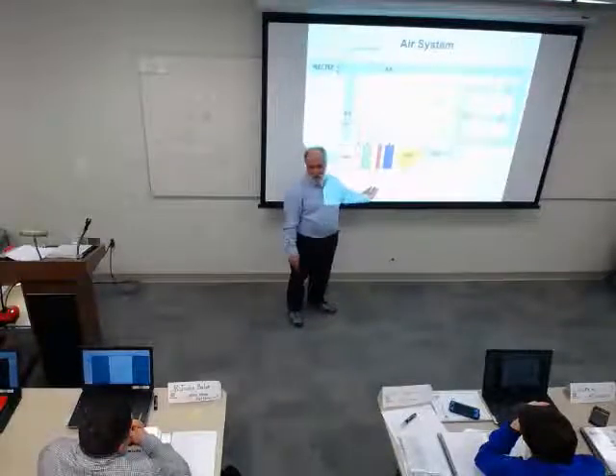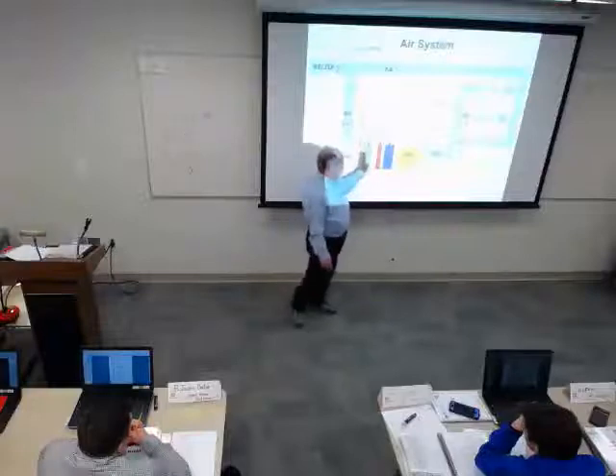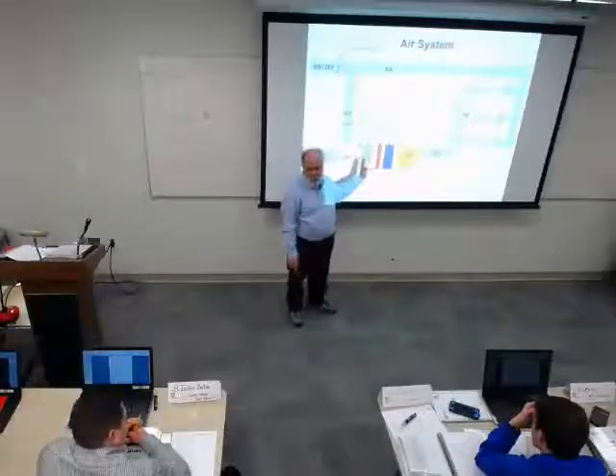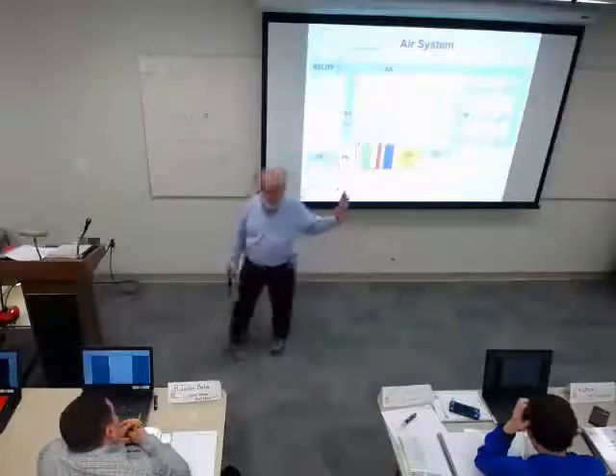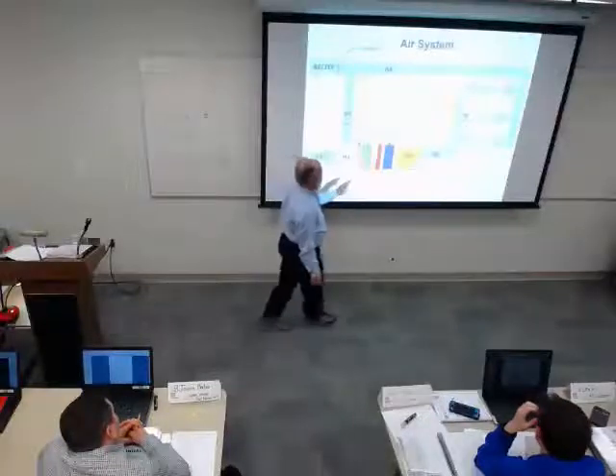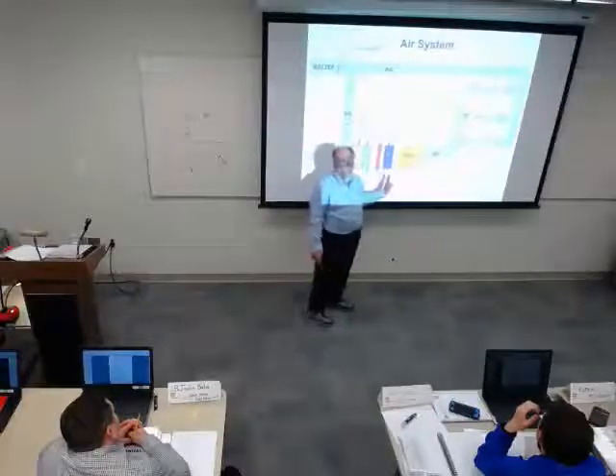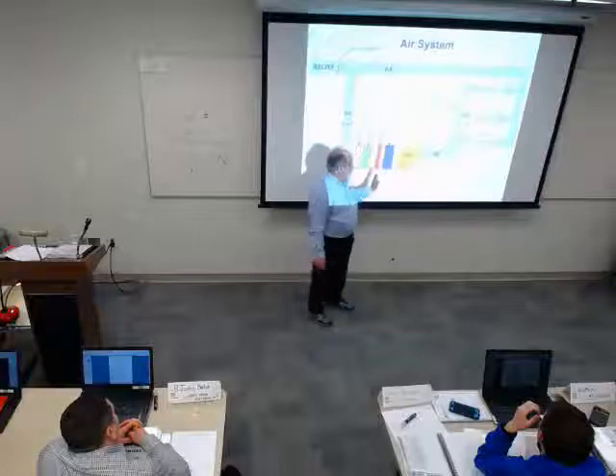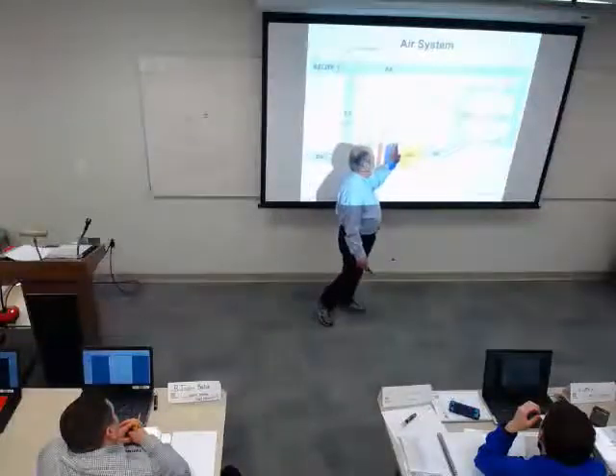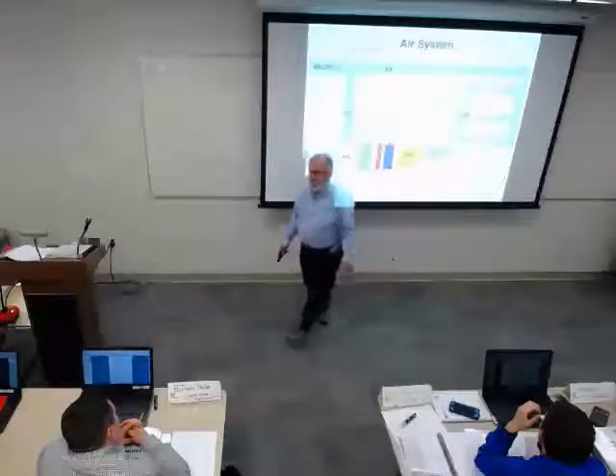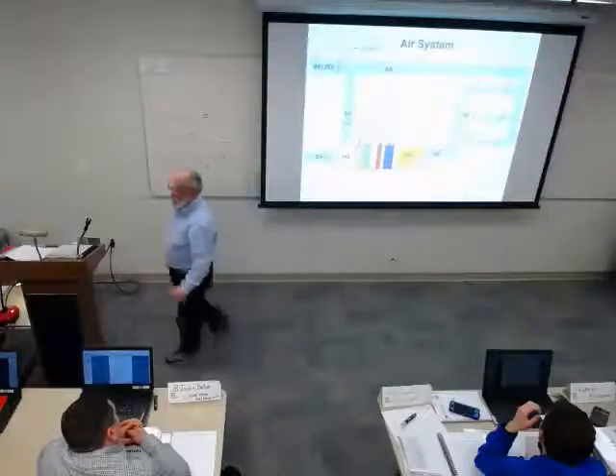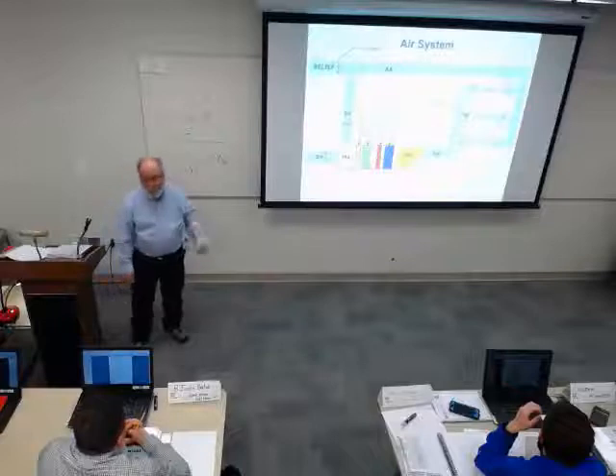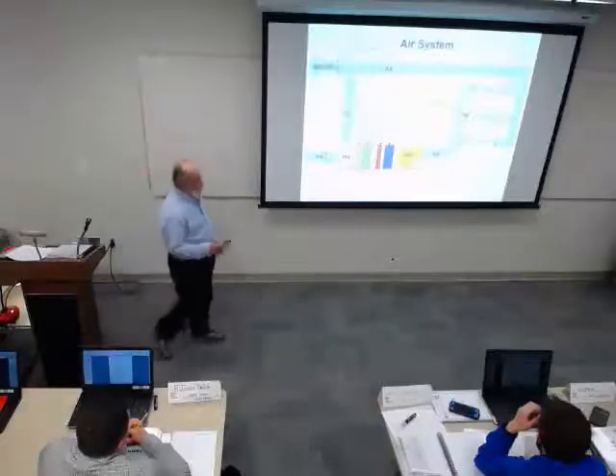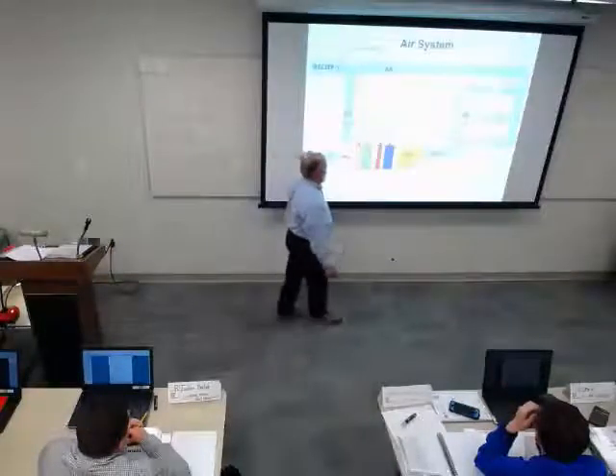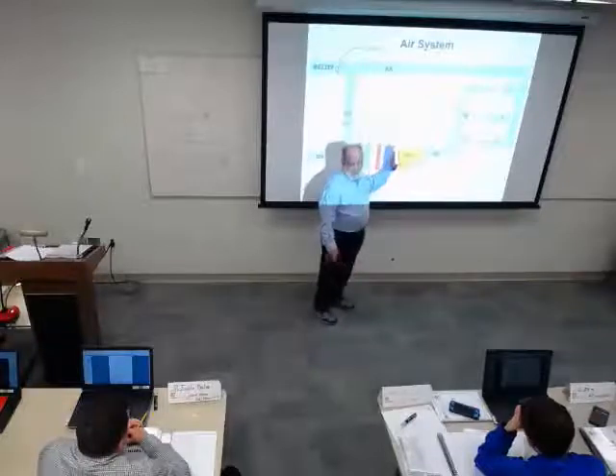And then we bring it through. This coil's in the preheat position. In this particular case, we would put it in the preheat position because we want to protect our cooling coil. Other than that, it really doesn't matter a lot. If we're trying to do humidity control, we may put it either here or another one downstream. When we do our psych charts, we'll talk about that, and I'll also talk about that, I believe, in the lab. But what I've found in our area is you really need to put it here to protect the coil.